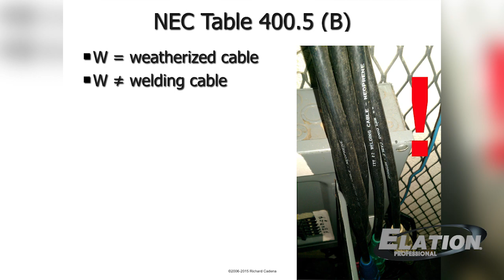But there are instances where I still see welding cable being used at certain production companies, either because they've had it forever, they continue to use it, or they're misinformed about what they should be using, or for whatever reason. And it still goes on today. So personally, I would never put welding cable into service because as a trained professional, I know better. And if there's an accident, if there's a fire, because welding cable is not rated for continuous duty use. It's got very fine strands, and so if you run it too much, it's going to overheat and it could cause a problem. And if that happens on my watch, then I would have a hand in responsibility. I don't want that liability. So personally, if somebody brought out some feeder cable and I had to do the tie-in, I would refuse. I would send that back, get me some proper cable, type SC or type W. So, something to be aware of.